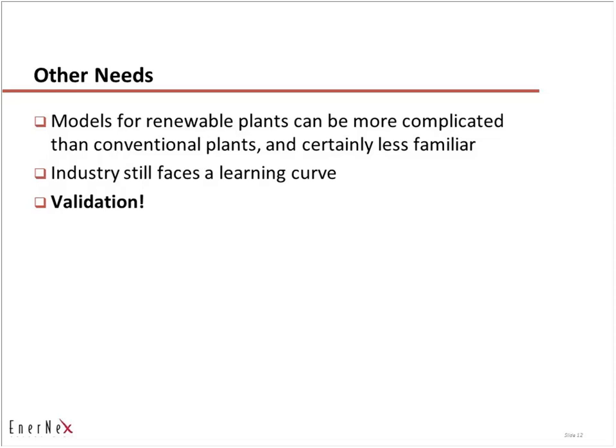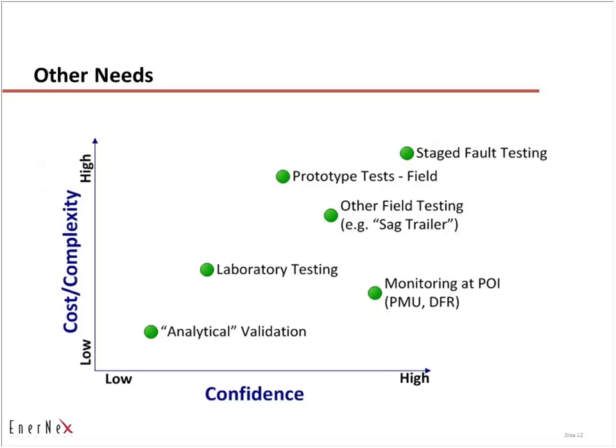Is it real or is it Memorex? We have models that, in the case of conventional generators, we have reason to believe represent actual facility performance pretty well. That question is much less answered for renewable plants. The scale and scope is daunting — there are probably more than 500 bulk-connected renewable plants in the ground. Plant model validation isn't just about whether GE has a good model for their turbine; it's about whether you've taken that model and constructed the appropriate representation for each of those 500 plants.